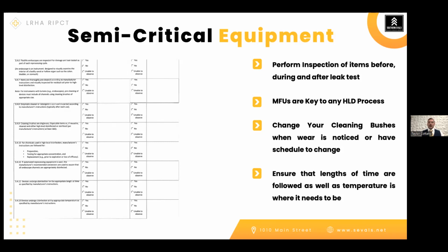And lastly, on this slide, make sure that the lengths of time that you're following, as well as the temperature, is where it needs to be. Many times whenever we talk about semi-critical equipment, we talk about high-level disinfection, and those chemicals have certain temperatures or certain lengths of time that they require for you to either soak items or flush items. Even make sure that the temperature is there if you're just disinfecting items. All those things, if we are respecting our MFUs, you have to follow those guidelines. Or if it's unfeasible, you want to look at another option for your different instruments.